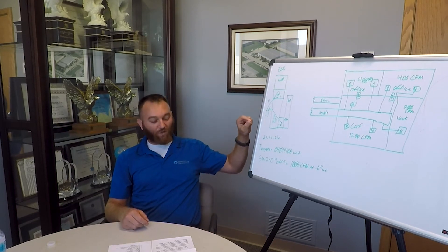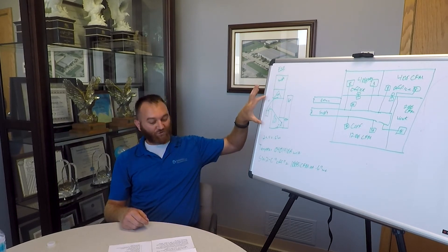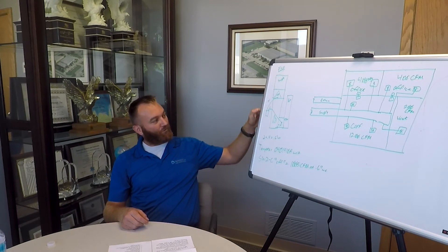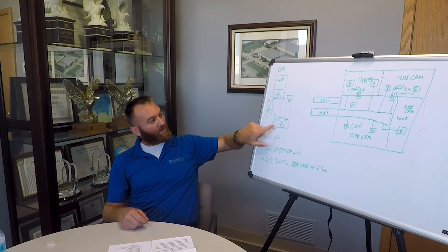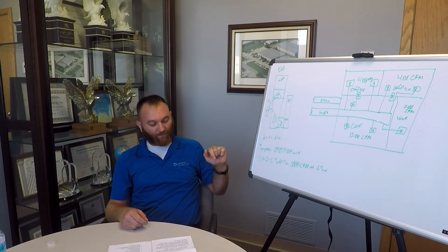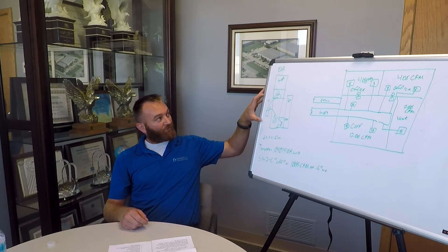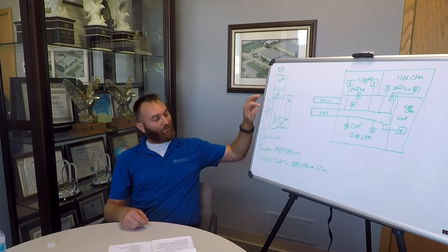Manufacturers will provide you with an external static pressure chart in the book. You will use a magnehelic or a digital manometer to read these negative and positive pressures. External static pressure is the resistance in the ductwork that the blower must overcome to move air properly.